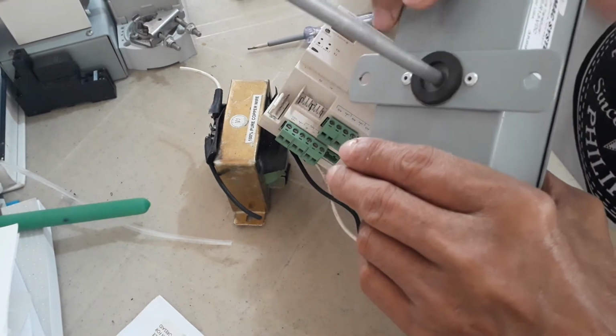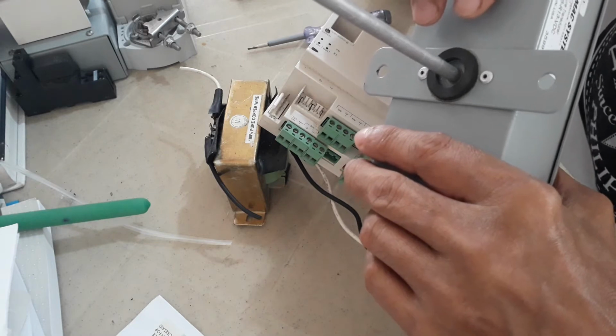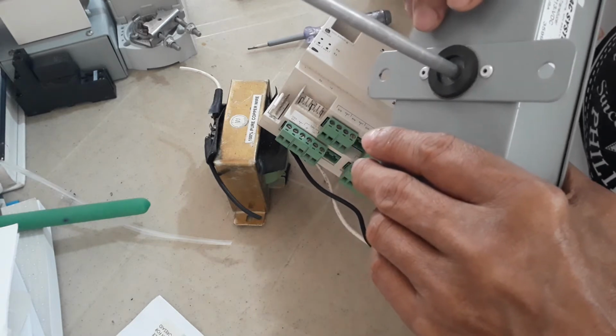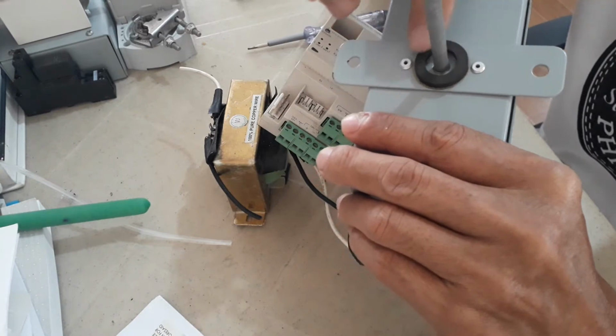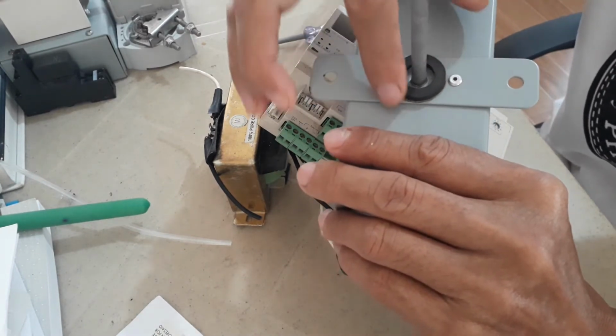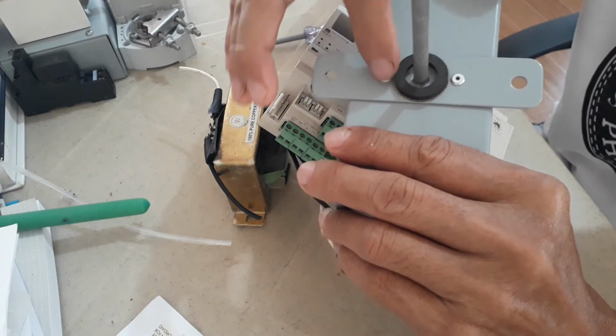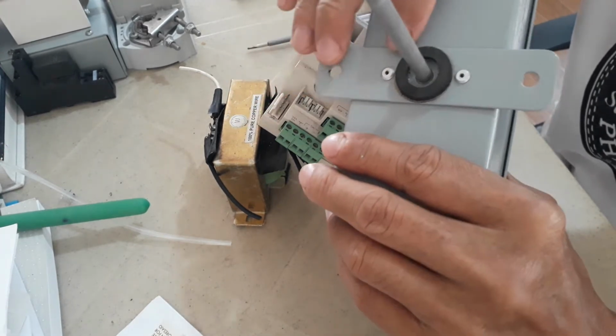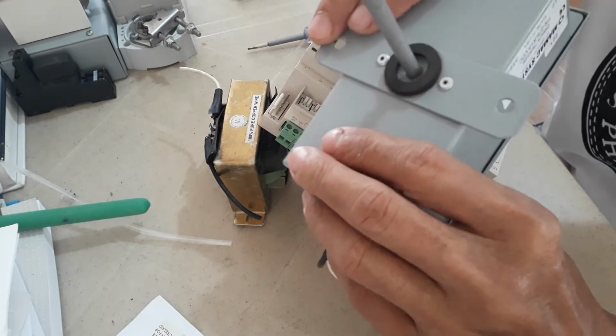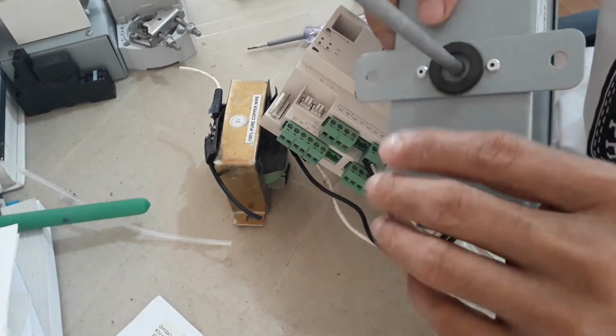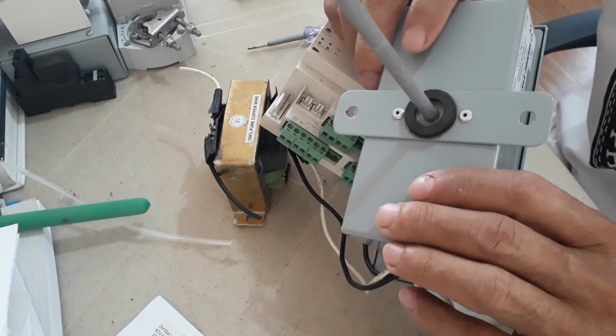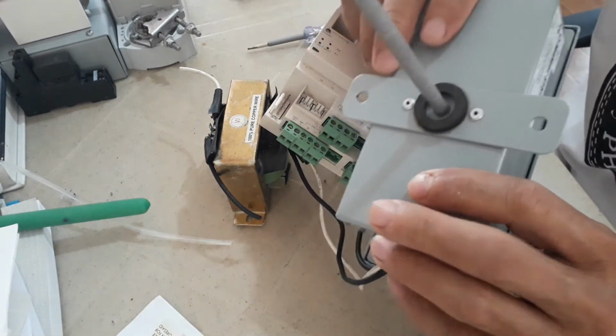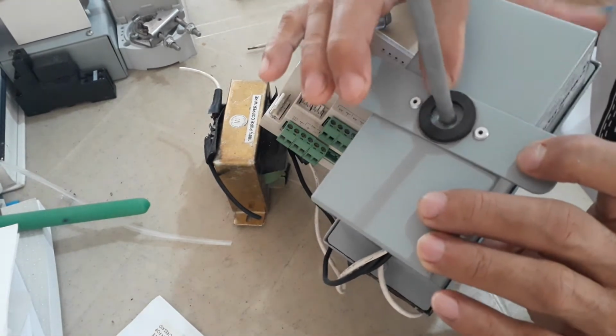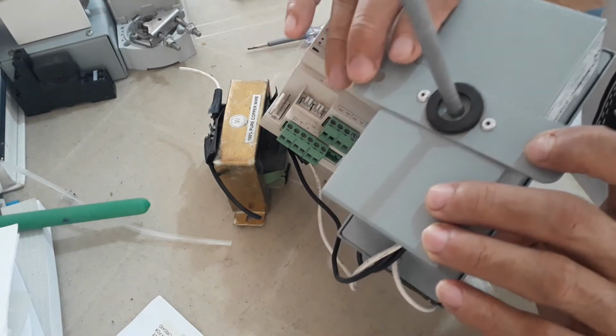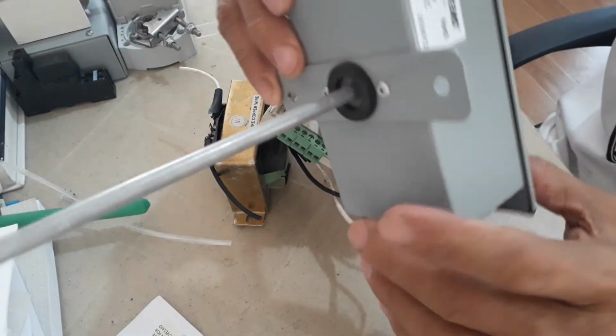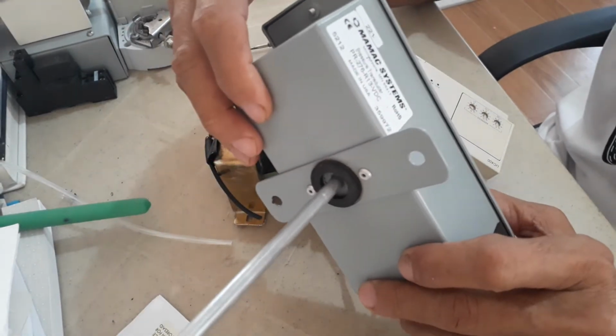So if you have an air handling unit or a staircase pressurization, if it is ducted, then you can bore a hole. Then make sure to insert this properly, and there is also something here, this one will prevent the air from exiting the hole, okay? So this is the probe. Insert it in the duct. First, provide a small hole that will fit this probe. Then make sure you also provide this gasket so the air will not leak, okay? So this is a duct pressure transducer, okay?